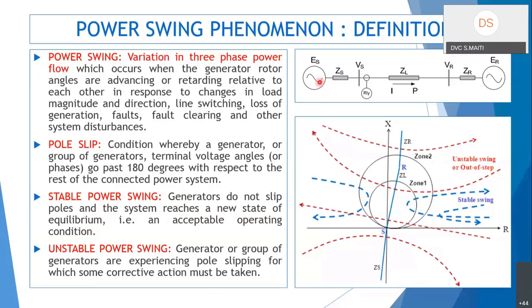For example, if power was flowing from S to R, with a big generator going out, the power flow may reverse. If the system settles into a new operating condition, we have a stable power swing. If it does not settle and continues to swing, generators experience pole slipping and corrective actions must be taken — that is an unstable power swing.